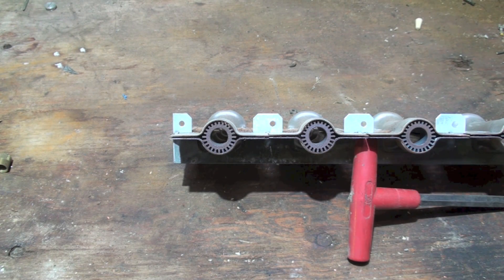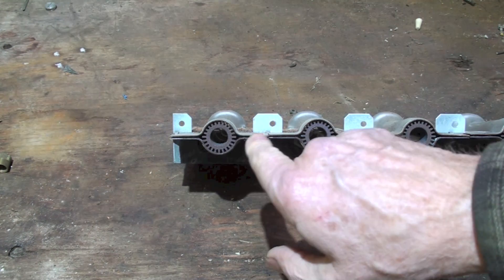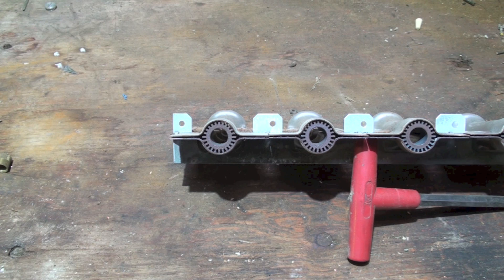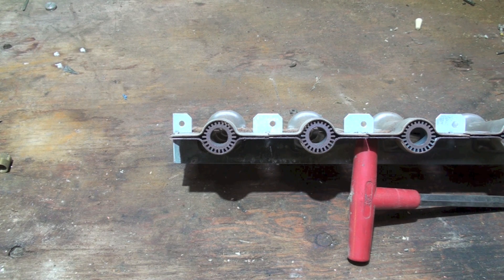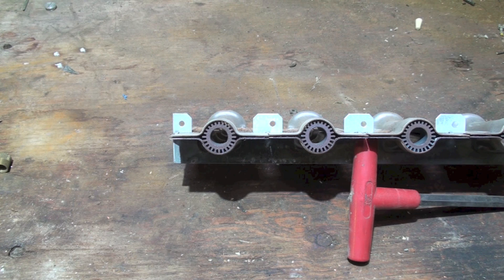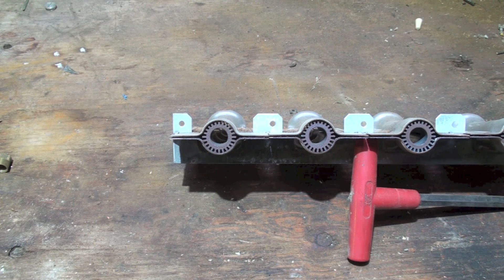If those things get plugged, like right in here, this one's kind of plugged up. If that happens, then it doesn't spread the flame. And you have to spread it to all the burners because the flame rod's on the last burner to light.